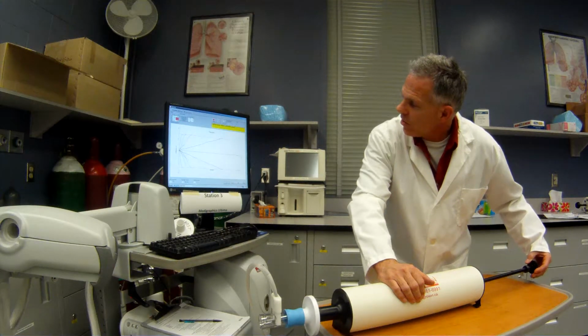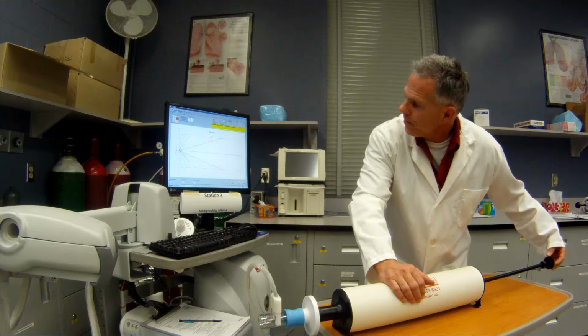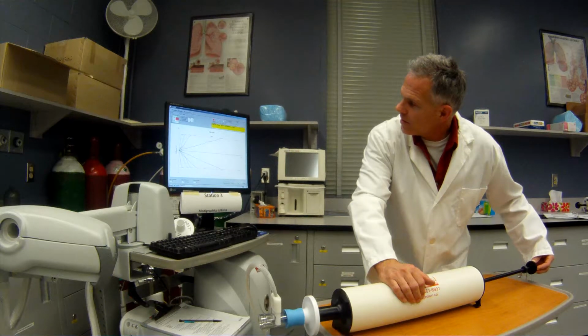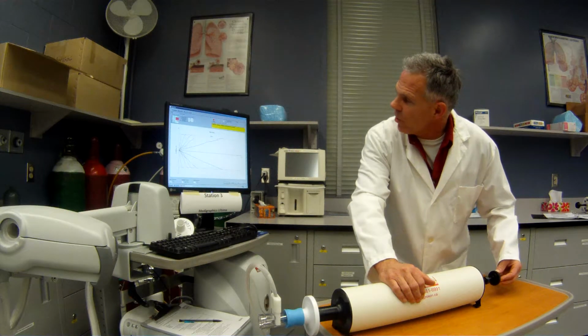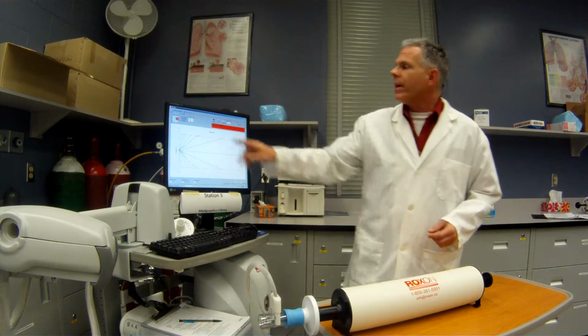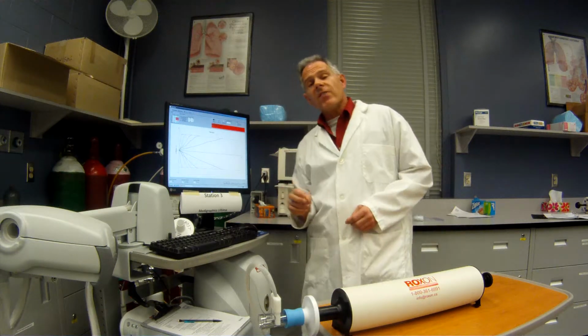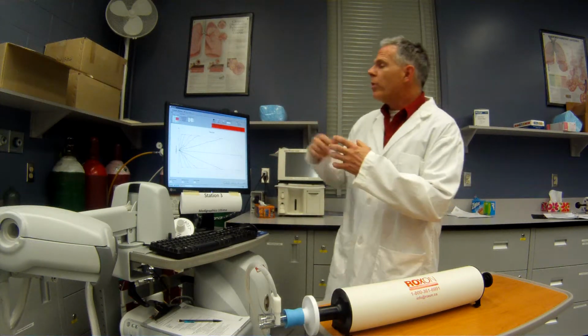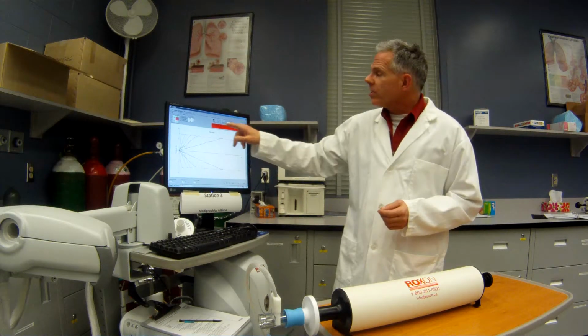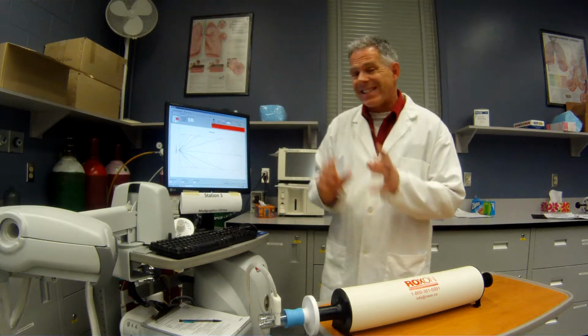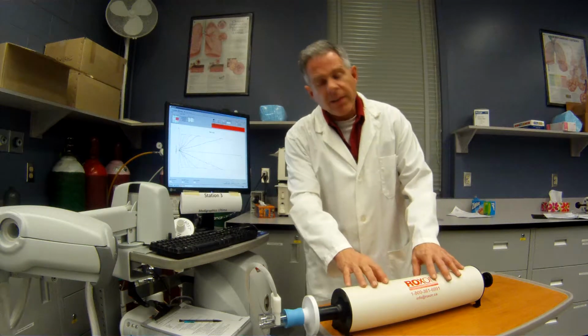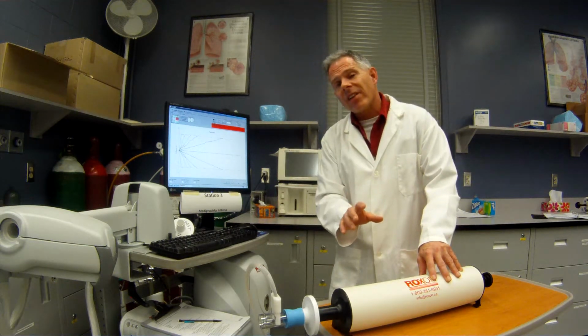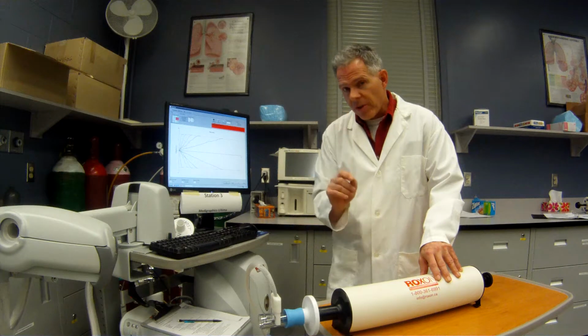So I'm just going to do a couple other flow rates here. And we'll do a nice slow, medium kind of flow rate. Yeah, a nice medium kind of flow rate. So this one here has already given me a warning. On my higher flow rates, it didn't calibrate successfully. Okay? But we repeat this a couple of times until this comes in and was measuring exactly the 3 liters as we need. Okay? It's important that it meet ATS criteria, and that's plus or minus 3%.